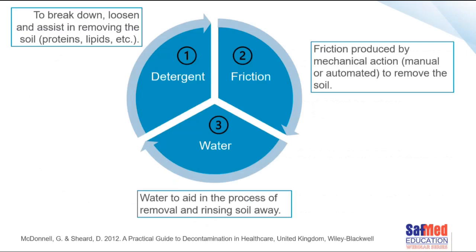As a reminder, we started our series with this slide about what is needed for cleaning to be effective — three important things. We need detergent to break down, loosen and assist in removing soils like proteins and lipids. We need friction, produced either by a manual action like rubbing and scrubbing, or a mechanical action like cavitation in ultrasonic cleaning or the force of water in a washer disinfector. And we need water to aid in removing and rinsing soil away, as well as wetting instruments. The end result is that instruments are at the very least visibly free from dirt, stains or impurities.